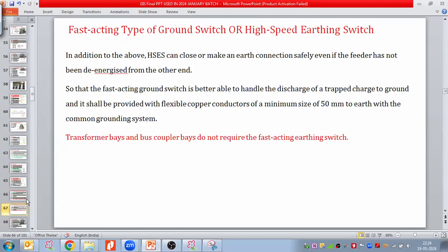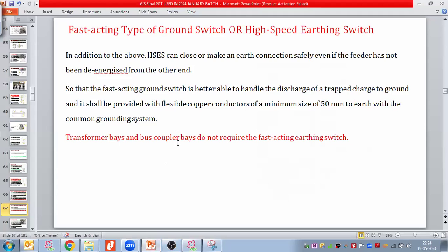In addition to the above, a high-speed earthing switch can close or make an earth connection safely even if the feeder has not been de-energized from the other end, so the fast-acting grounding switch is better able to handle discharge of trapped charge to ground, and shall be provided with flexible copper conductors of 50 square mm to earth with the common grounding system. Transformer bay and reactor bay do not have such a long overhead transmission line, so the trapped charge will be very less. So in those kinds of bays, there is no need to consider the fast acting earthing switch. Am I clear on why we take the high speed earthing switch?